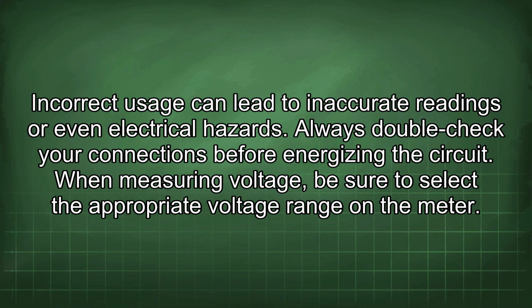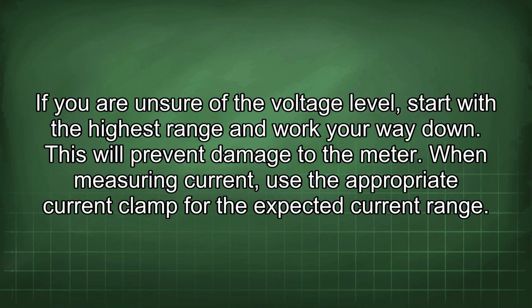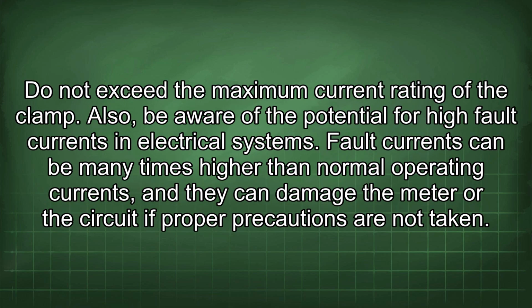When measuring voltage, be sure to select the appropriate voltage range on the meter. If you are unsure of the voltage level, start with the highest range and work your way down. This will prevent damage to the meter. When measuring current, use the appropriate current clamp for the expected current range. Do not exceed the maximum current rating of the clamp.